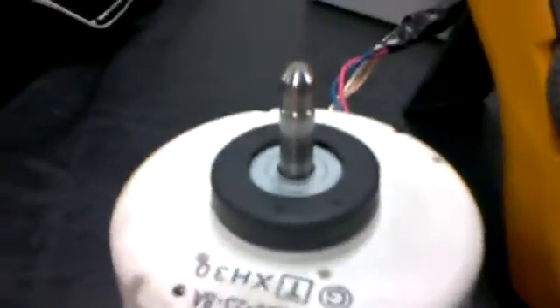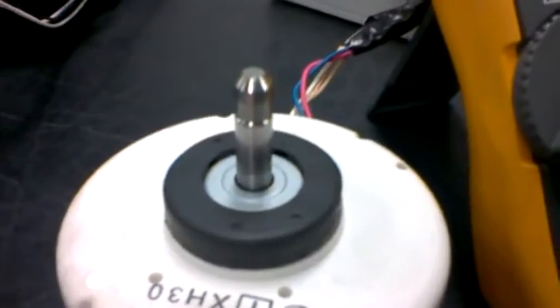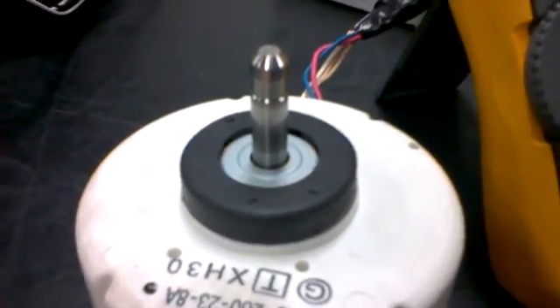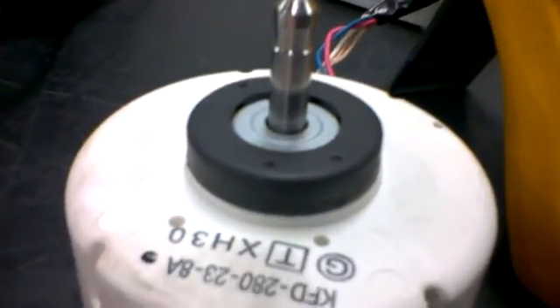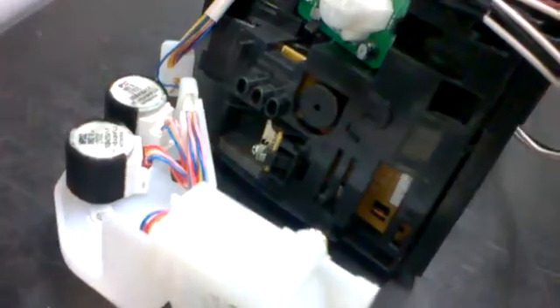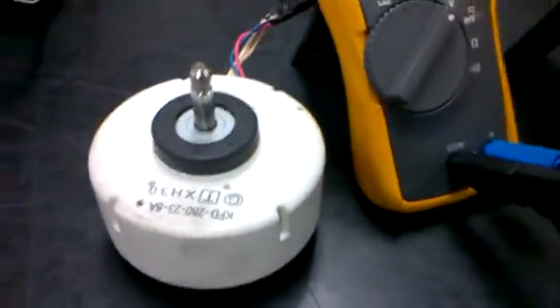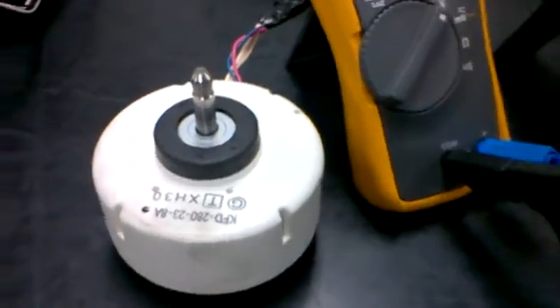Now remember with service testing, you should always check with the manufacturer's brand and their required service testing information, and what they recommend as best practice. This will shut down in a minute, and it has. And if we have a look over here, you'll see that we now have an active fault, which if I use an alphanumeric diagnostic code, it'll certainly tell me that there's a fan position lock.